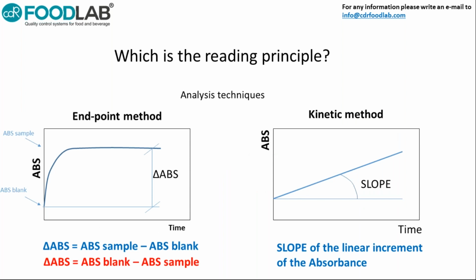What is the reading principle? We have two kinds of techniques. The left one is an endpoint reaction, so we add into the cuvette the sample or another reagent, for example, that is, of course, in the package, ready. We read the blank, we read the starting point, the first level of the absorbance. After that, we add another reagent that starts the reaction, and after 10 seconds, 5 minutes, 10 minutes maximum, of course this depends on the kind of chemical reaction, we read the absorbance again. So from this is the delta of absorbance that is our signal in this case, and this delta of absorbance will be connected to the concentration.